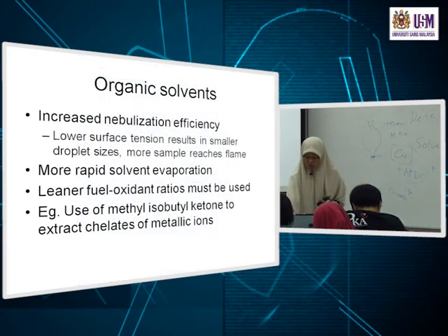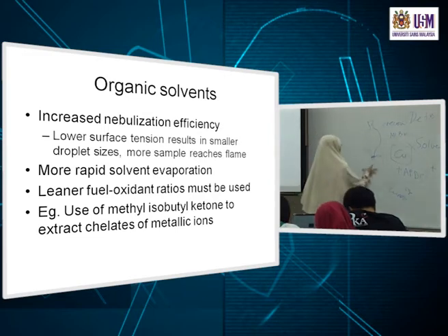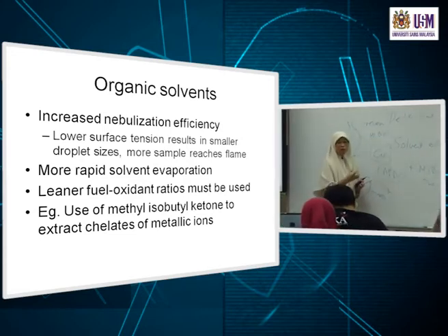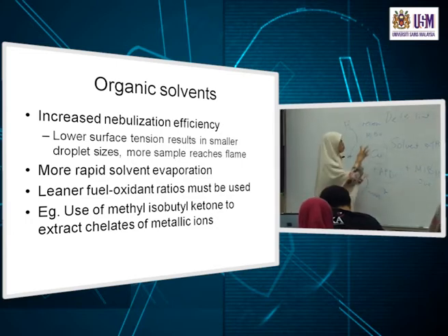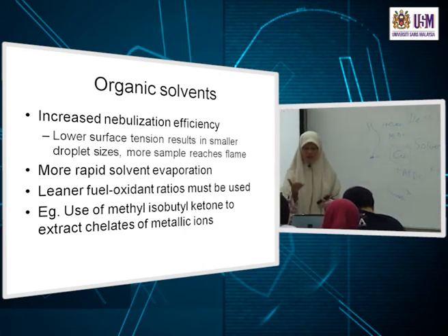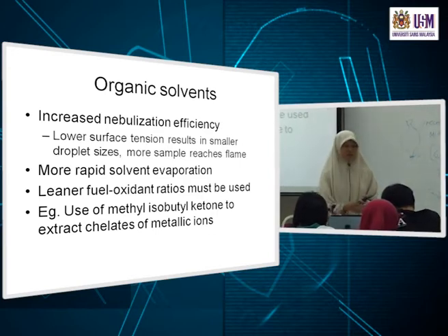Other than the fact that you want to pre-concentrate, you will also get increased nebulization and increased atomization, plus the fact that you are now introducing MIBK, an organic solvent, into the flame. This also acts like a fuel, so you have to reduce your air acetylene when you run an analysis of elements in MIBK.